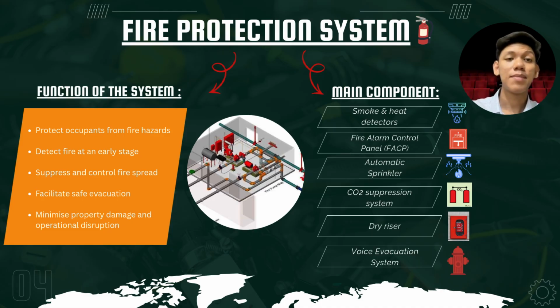Next, I will explain the main components of the fire protection system. The first component is the smoke and heat detector, which detects smoke or high temperatures and sends a signal to the fire alarm control panel. The fire alarm control panel, or FACP, acts as the central control unit that can monitor and manage the entire fire protection system. The next component is the automatic sprinkler system, which can help control the fire by releasing water automatically when the temperature becomes too high.